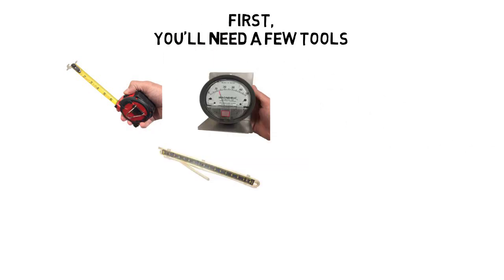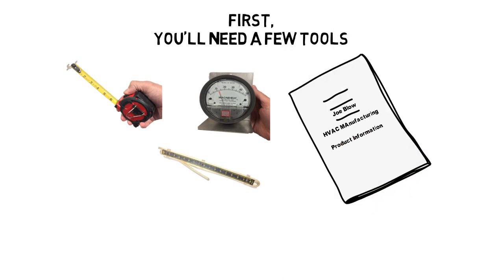Second, a magnehelic or a U-tube manometer, something to measure static pressure. And number three, the manufacturer's product data with a fan curve in it for the unit you're working on.